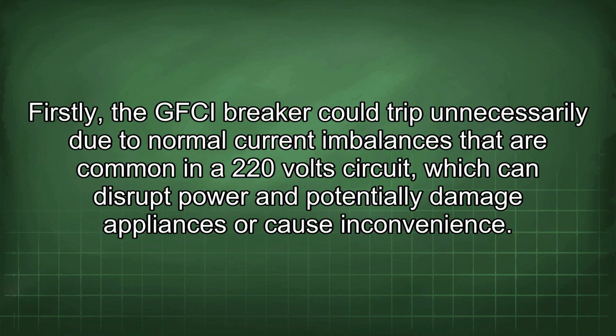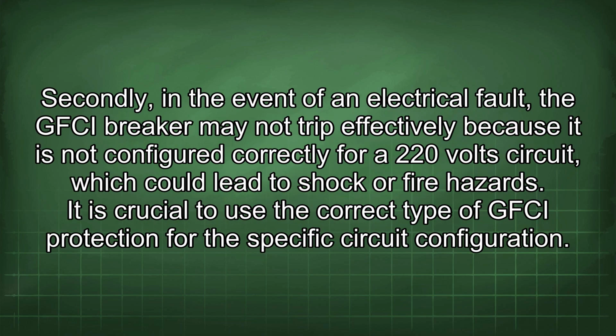Firstly, the GFCI breaker could trip unnecessarily due to normal current imbalances that are common in a 220 volt circuit, which can disrupt power and potentially damage appliances or cause inconvenience. Secondly, in the event of an electrical fault, the GFCI breaker may not trip effectively because it is not configured correctly for a 220 volt circuit, which could lead to shock or fire hazards.